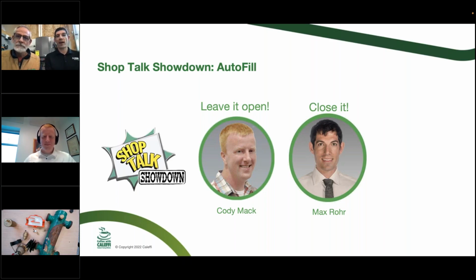So the longer you do that, the higher the likelihood you get to a catastrophic issue, which is that you have to replace the multi-thousand-dollar heat exchanger in a boiler. It's a drag to have to go back for a callback. It's a bigger issue if you have to go back and say, I'm sorry, Mr. and Mrs. homeowner, the heart of the system, we have to throw it in the garbage, and it's not going to be covered by warranty, and you're going to have to put in a new one. So Cody, I can see.